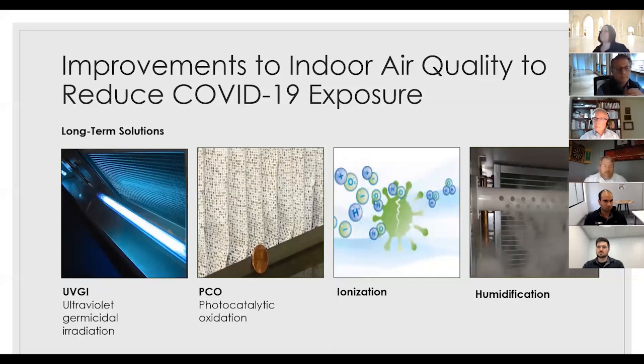That reminds me of another point. A lot of manufacturers and sales companies are promoting putting UVGI in long straight runs of ductwork. But as Greg pointed out, the issue is it doesn't have enough residence time for the particles carrying the virus to actually kill them. You'd need a really long run, anywhere from 30 to 100 feet, depending on the velocity of the airflow, which makes it cost prohibitive and impractical in a lot of cases, since there isn't that much space in many buildings for that kind of straight duct run.